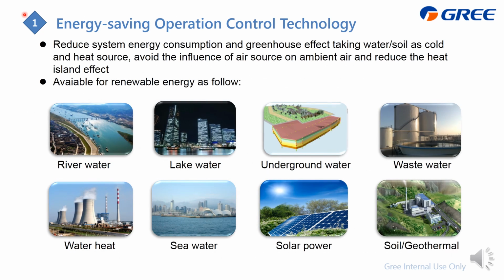And for the water, instead of the cooling tower for cooling and boiler for heating, we can use the water, for example, from the river, from the lake, or the underground water, or the sea water. We can also use it to cool down or heat up the water system. And for that, we can improve the system efficiency, especially to avoid the influence of the air source on ambient air and reduce the heat island effect.